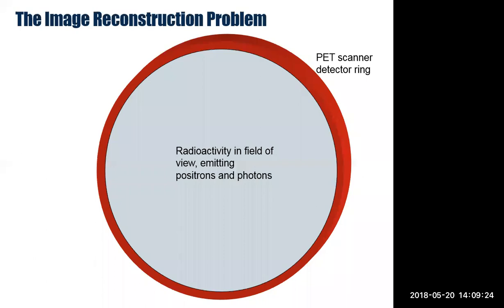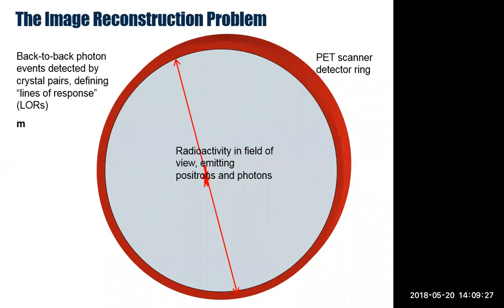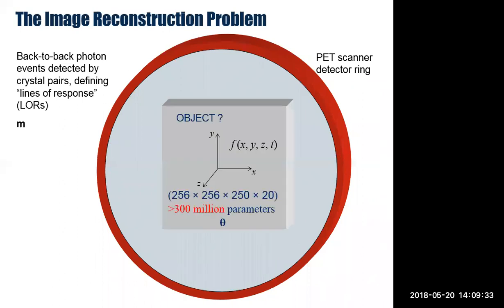Looking at that again from another angle: we've got an unknown radioactive distribution inside the PET scanner, and here we see a few example back-to-back photon pairs being emitted, detected by the ring of crystals around the patient. The goal of image reconstruction is to estimate that radioactive concentration just from those detections. We could typically have anywhere from 100 million up to 1 billion such back-to-back photon pairs from which we reconstruct the 3D distribution of the radiotracer.